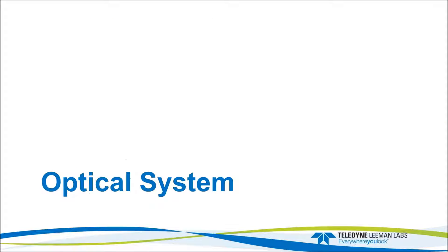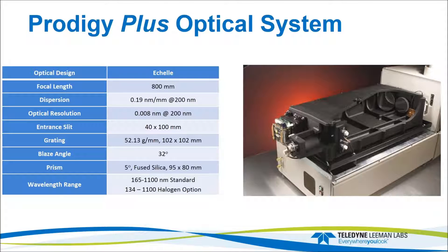The Prodigy Plus optical system is the same as used on the Prodigy system — an 800 millimeter focal length system. Important features highlighted are focal length at 800 millimeters, dispersion (a property of the Echelle optical system we take advantage of by using a large detector), and the wavelength range. The standard wavelength range is 165 to 1,100 nanometers.